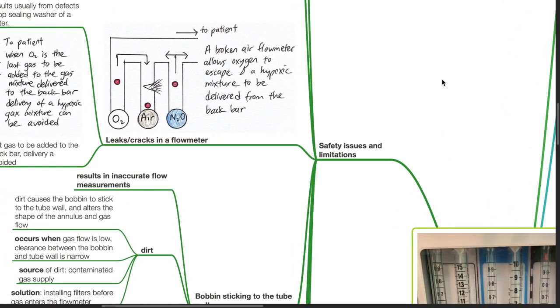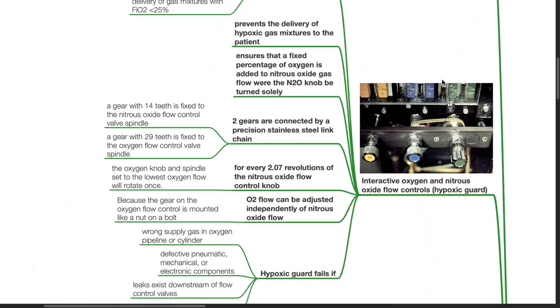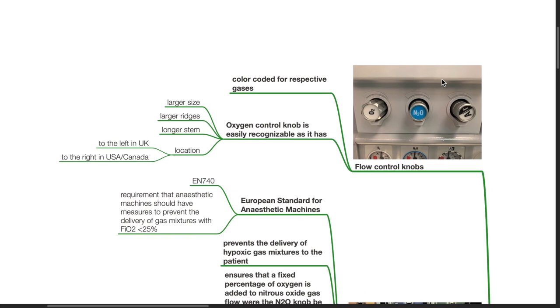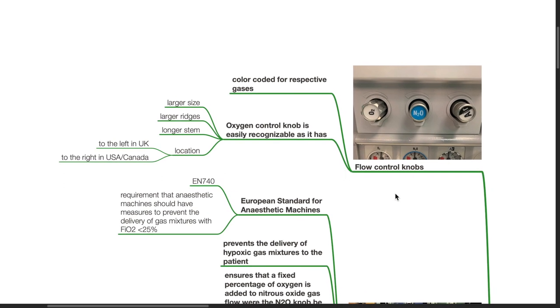Safety issues and limitations: Flow control knobs are color coded for respective gases. The oxygen control knob is easily recognizable as it has a larger size, larger ridges, longer stem, and it is located to the left in UK and to the right in USA and Canada.